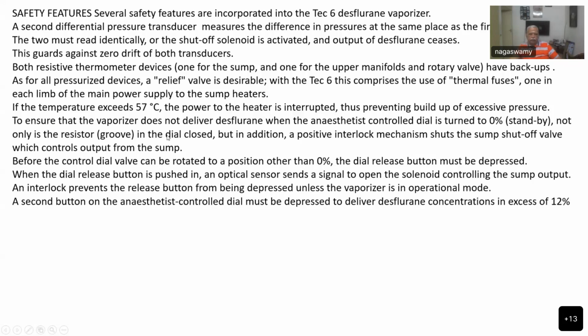To ensure that the vaporizer does not deliver desflurane when the anesthetist control dial is turned to zero, that is the standby mode, not only is the resistor, that is the groove in the dial, closed, but in addition a positive interlock mechanism shuts the sump shut-off valve also, which controls the output. So the shut-off valve, which I showed in the earlier picture outside the sump, has two mechanisms. One, it will shut off automatically if the temperature heats up, or if the interlock mechanism is in zero, then the shut-off valve also will close.